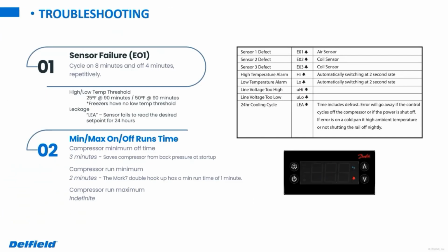So that's normally something that we'll find. If we go through and check that coil probe reading and it's not out of range, let's say it's reading exactly where it should be, then at that point that leads us to, okay, we may have a refrigeration issue, maybe we have an airflow issue with a bad evaporator fan or something along those lines. So those are just how we would start out as far as the troubleshooting goes. So with that LEA, again, the first thing I would have you do is check that evaporator. Is the evaporator froze up? If the answer is yes, then we're going to do a real-time probe reading and go from there as far as the troubleshooting goes.